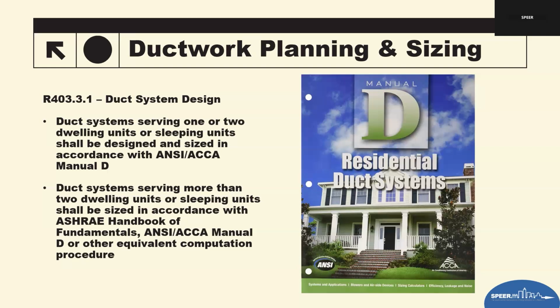You need to look for friction rate, available static pressure, room by room airflow. We'll talk about all this later on today. Duct sizes that match the design conditions or design calculations. A distribution layout matching submitted loads. Basically saying this is kind of how my ducts will run. This is how many Ys I have. This is the size of the duct. This is the CFM per room that we're doing. So these documents confirm the system was designed, wasn't just guessed or copied from a previous project. It's actually per the project being developed or asked for permit.